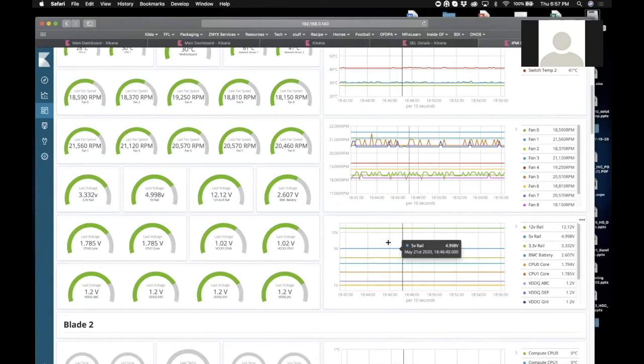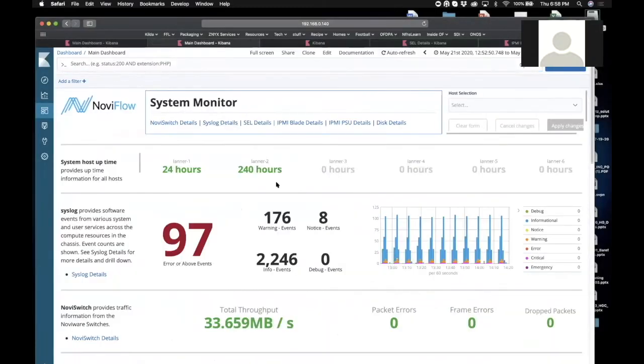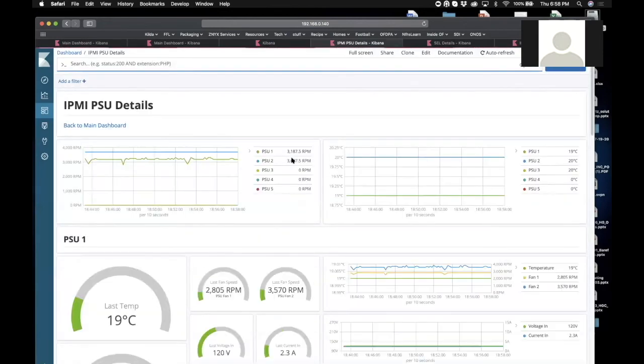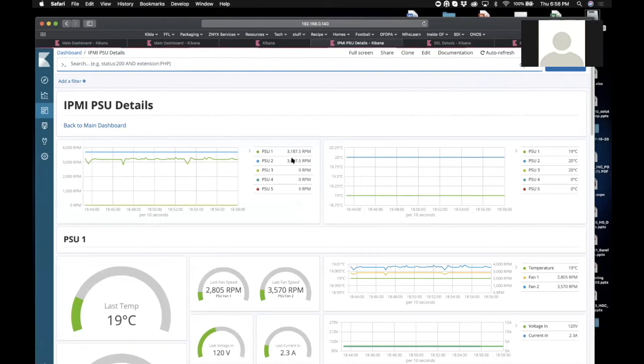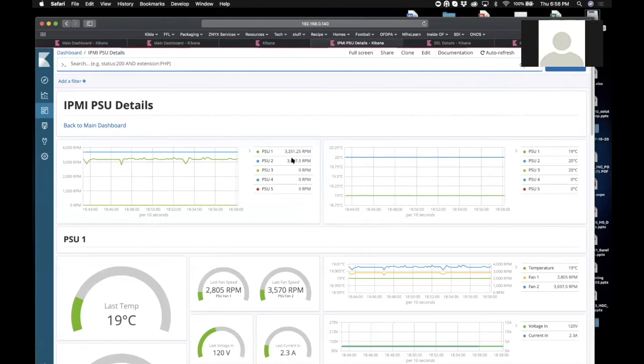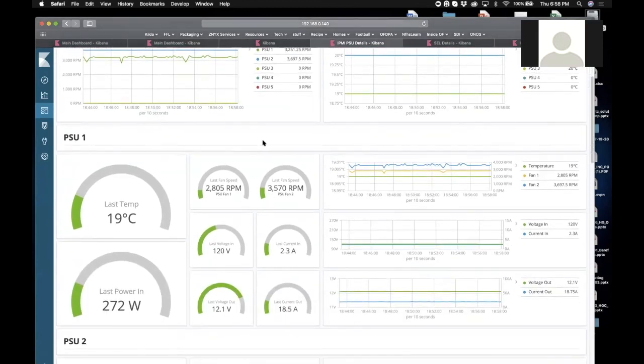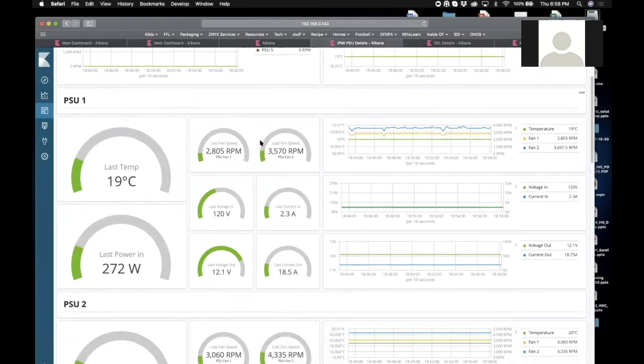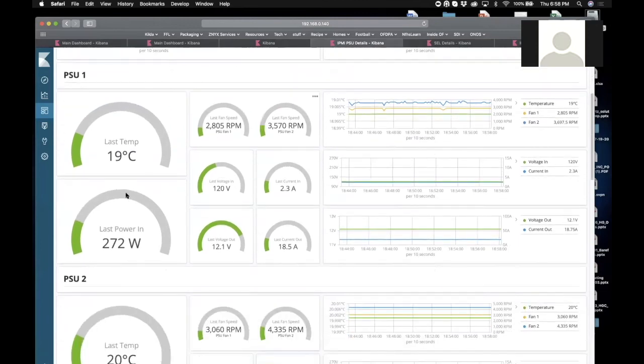Back to the main dashboard we have the power supply information. And remember I said earlier that there's something wrong with the platform, I got a red on the main dashboard, so we know that there's something going on in the power supply. If I were coming in first thing in the morning and I wanted to check the system, I see that and I go well before I get my coffee I got to check.